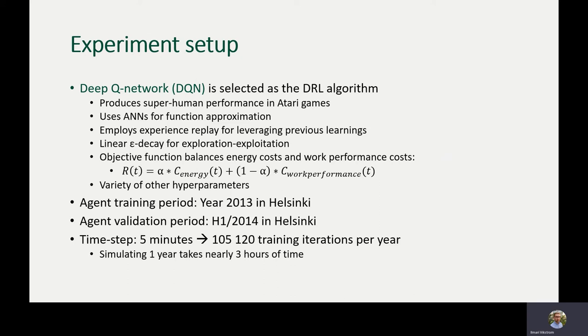For the exploration/exploitation trade-off we are going to use a linear epsilon decay function. As an objective or reward function, we are going to take into account both the energy cost — the energy used by the HVAC machinery — and the work performance cost, which stems from sub-optimal thermal conditions inside the building. The energy costs are calculated by multiplying power usage by the current electricity price, and the work performance cost is calculated by a model that depicts how work performance deteriorates when moving away from the optimal temperature zone.